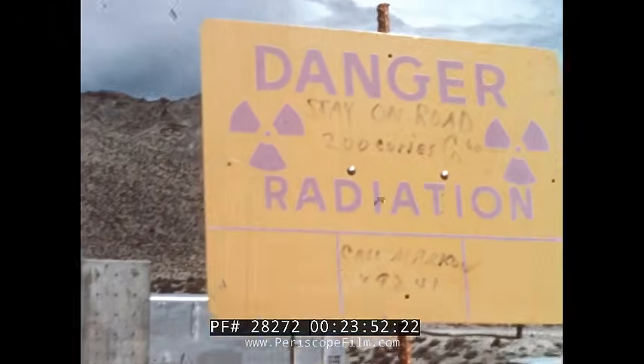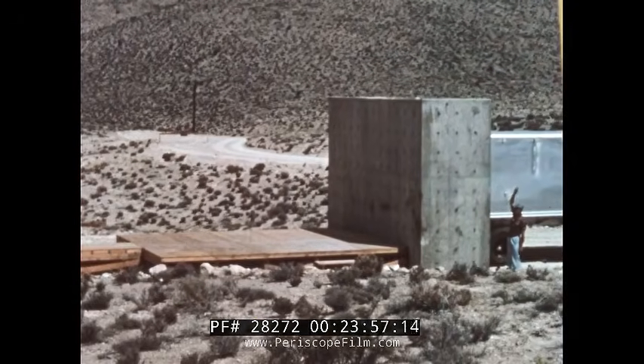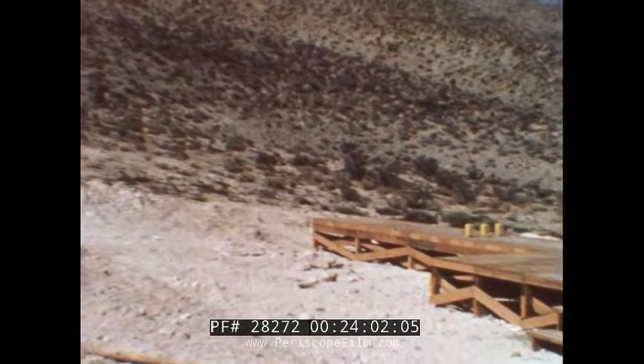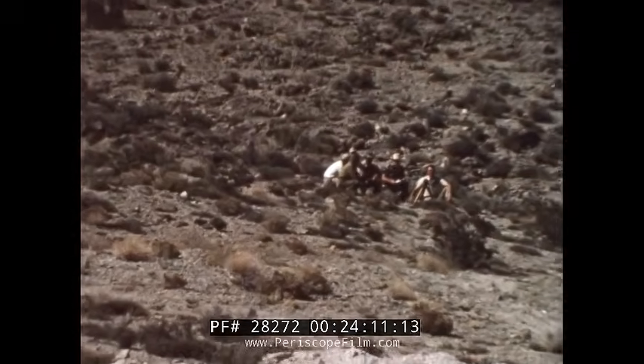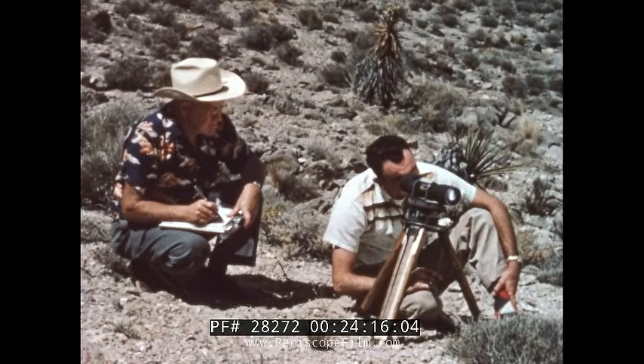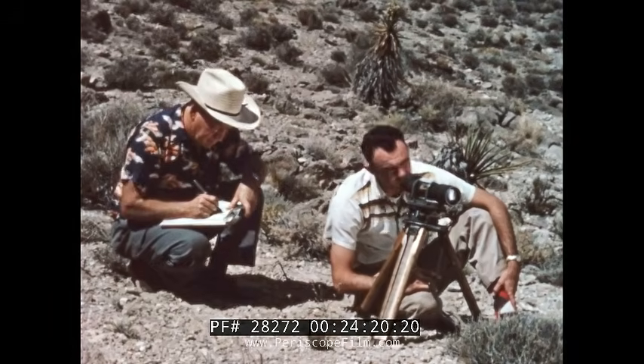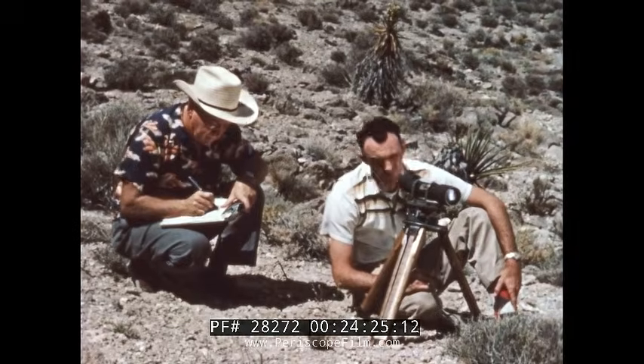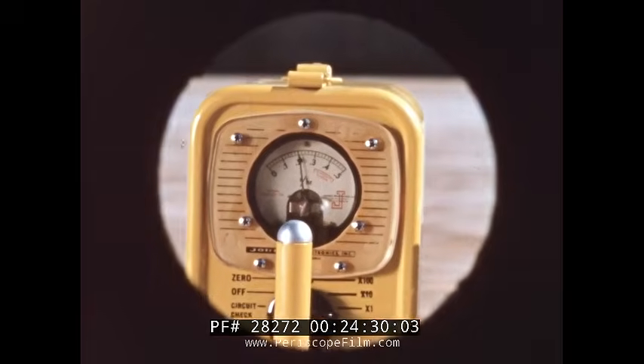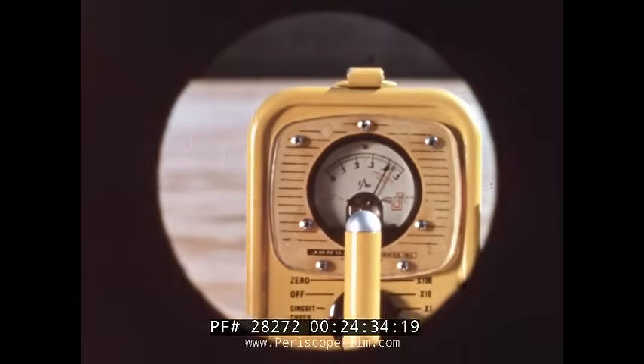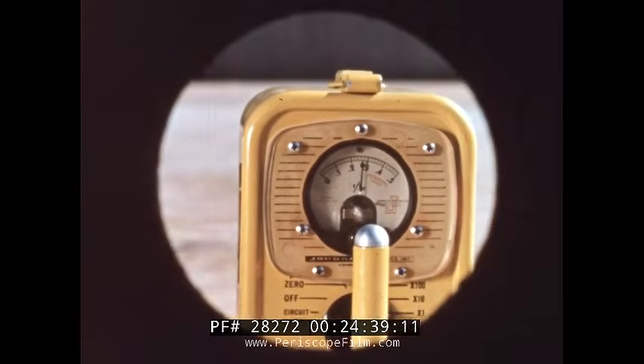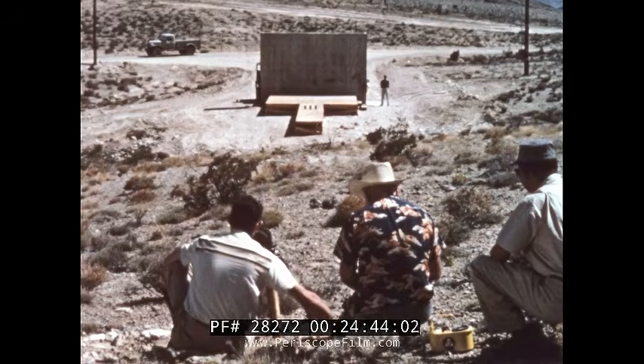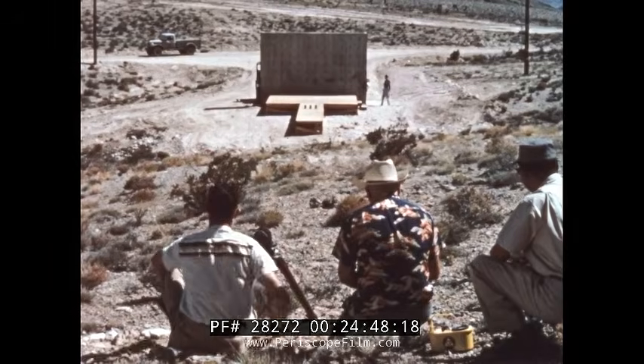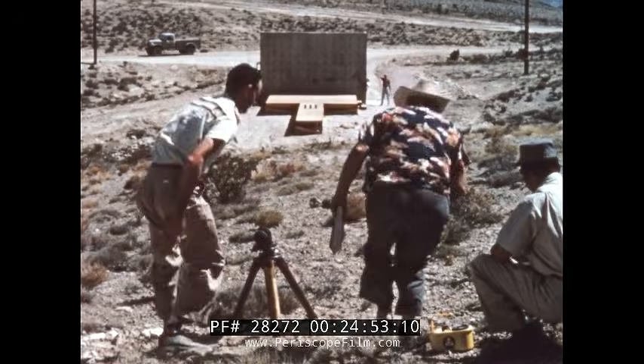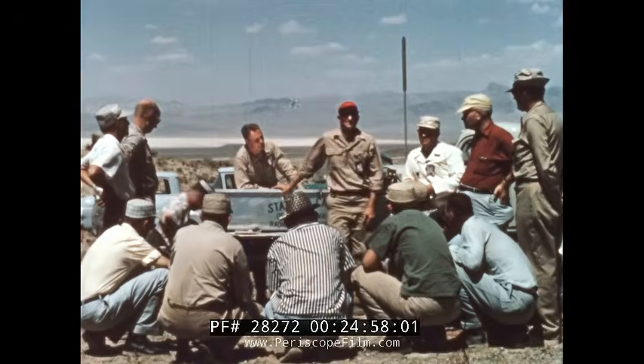but warning signs and massive concrete shielding indicate the use of a source of much greater intensity. Beyond this shielding, radiation from the 200 Curie source in use here is so intense that it is necessary for calibration to be effected through the use of a telescope. Time and care are necessary ingredients of this operation. Before the monitor can make an adjustment or move the meter, the source must be lowered into a 4,000-pound lead pig beneath the platform.